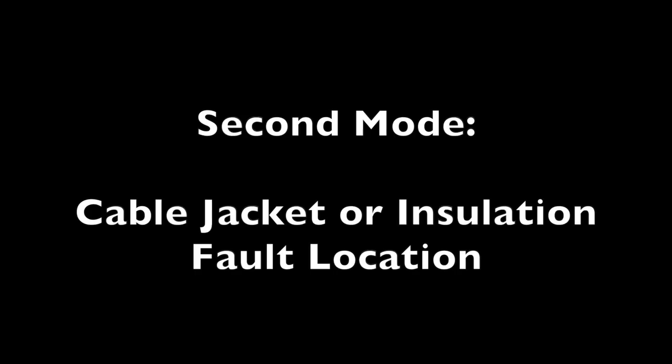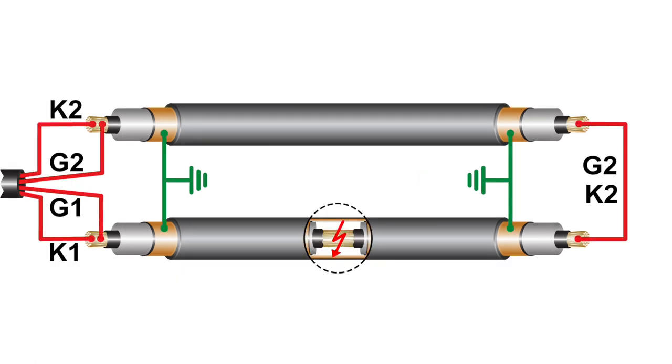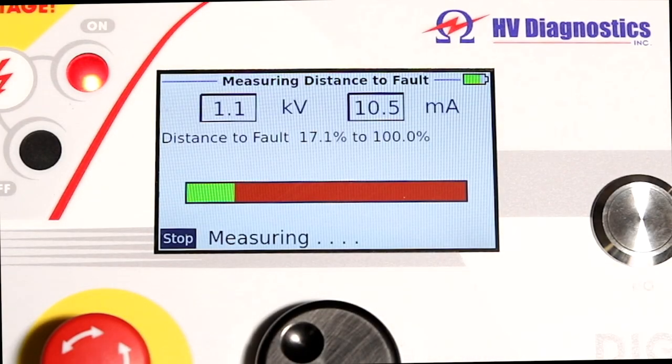The second mode is used to find the fault in the cable — either the fault in the cable jacket identified in the first test, or a fault in the cable insulation. This fault location mode will determine the exact location of the fault, effectively pre-locating where the fault is in the cable. This allows the user to quickly identify the location or section where the fault is, which is particularly useful when you have very long cable spans.